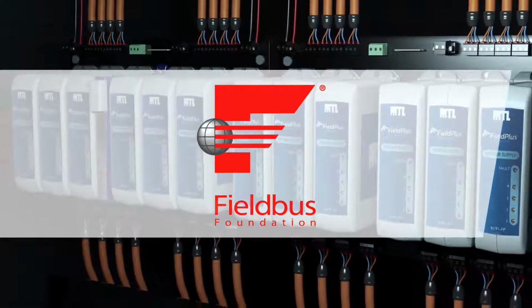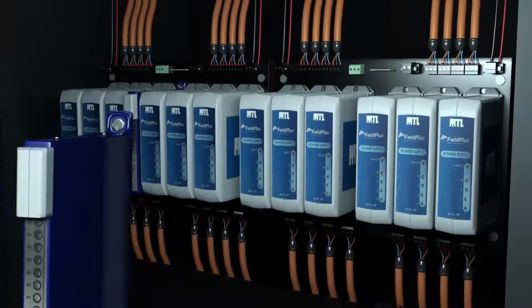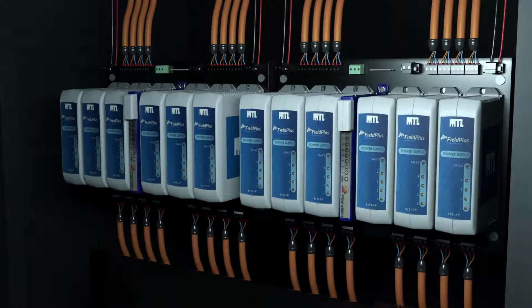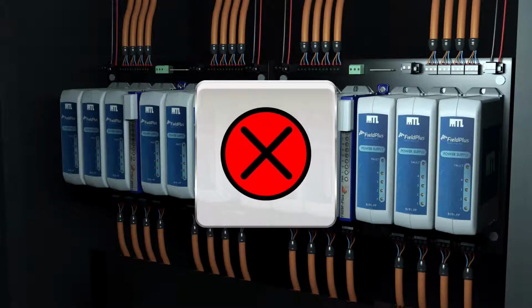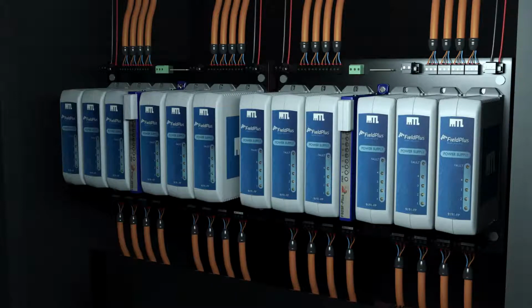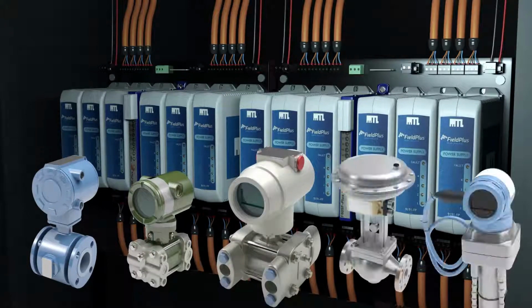Foundation Fieldbus is widely used in the process industries as a digital network for the control of field instrumentation. It delivers true multi-drop capability and high signal integrity. Diagnostic information on the health of instrument sensors and actuators is provided in real time to indicate a good, bad, or uncertain status for each measurement. However, the network itself is at risk if the physical layer electrical network is not robust. Here, failure could lead to the loss of complete segments containing multiple field devices with the risk of lost production.